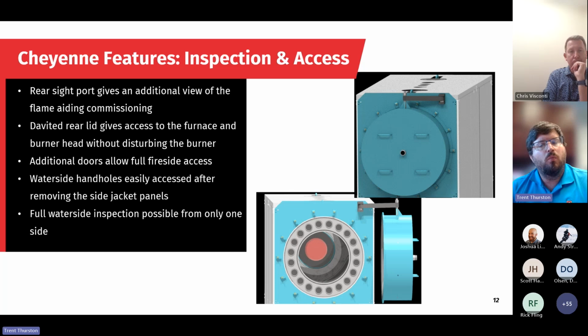So one of the things that we do like about our boiler is that we have a rear sight port in that davitted, rear-opening lid. For a sight port, everyone does have the one at the burner at the front, but the rear sight port gives another angle for a burner technician, so they can help with the commissioning and any maintenance or tuning. This rear sight port will give them a better picture and let them get a better idea of what's happening inside the flame and combustion.